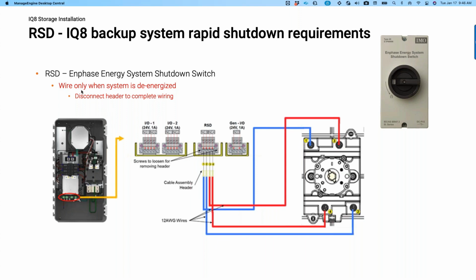So the first important note here is you should, and this is in red letters, wire only when the system is de-energized. So you really should shut this off. Go ahead and tell the homeowner, all right, I've got to wire this one other switch in. We're going to have to bring your home down for about 5 minutes when I wire this in. All right, and you want to make sure that you wire this when it's de-energized.